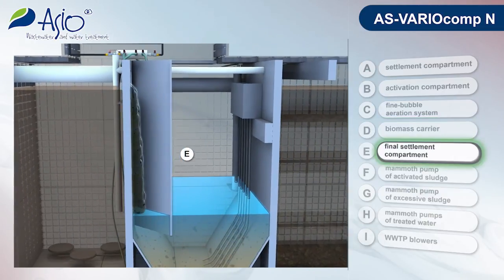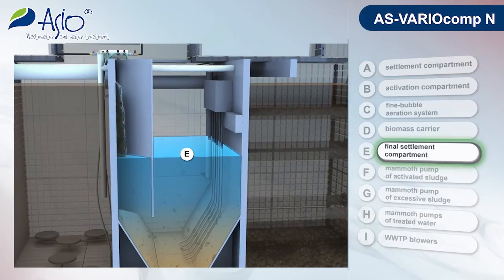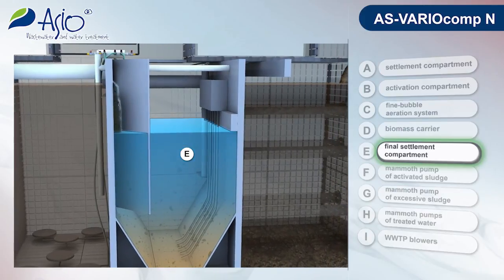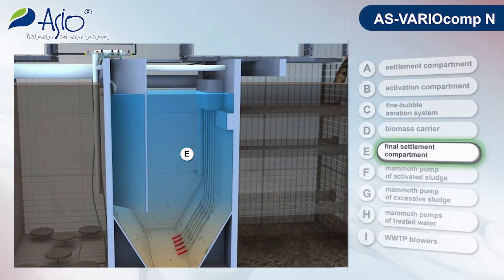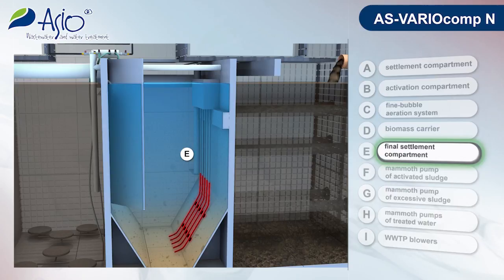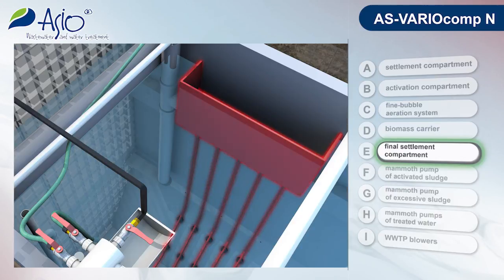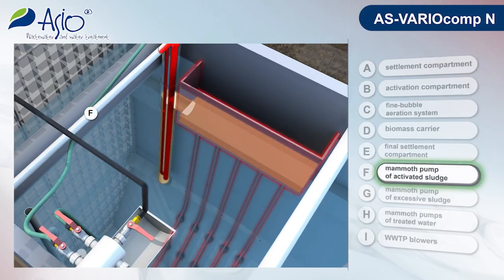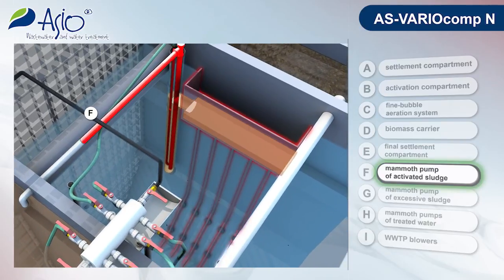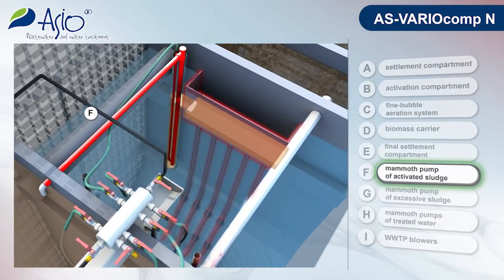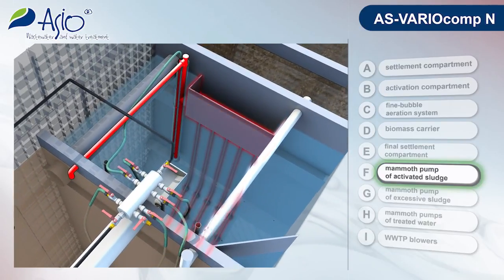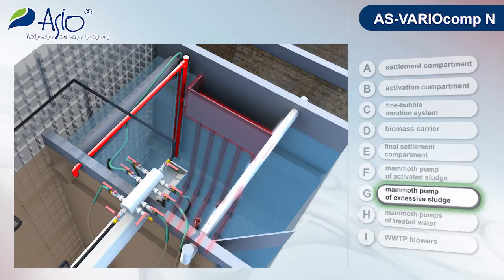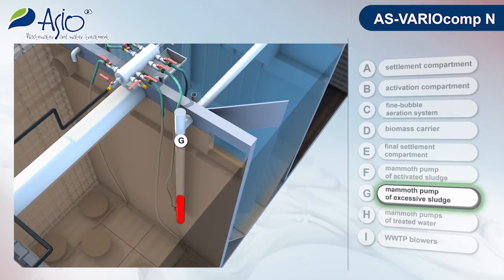Activated mixture from the activation part flows into a vertical final settlement tank where activated sludge and treated water are separated. Separated activated sludge is redrawn to the activation process by a mammoth pump, and excessive aerobically stabilised sludge is directed to the sludge compartment.